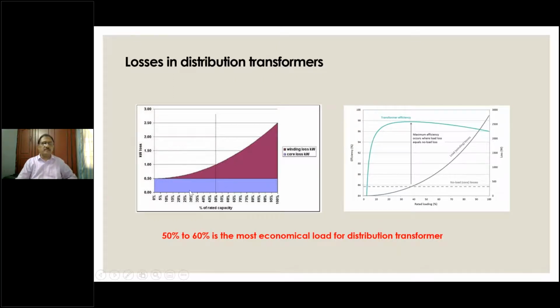Like I already mentioned to you, you have iron losses, which are called fixed losses. You have winding losses or copper losses, which are variable losses. Where they meet, at approximately 50% load, the best efficiency will occur. But typically in a designed transformer, 40% oil cooled will be the best efficiency.